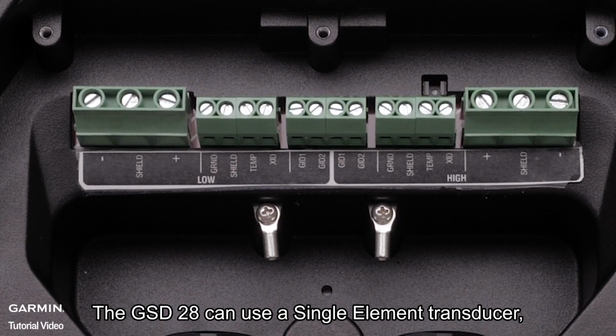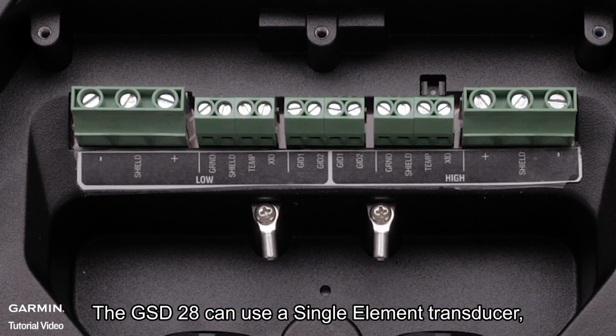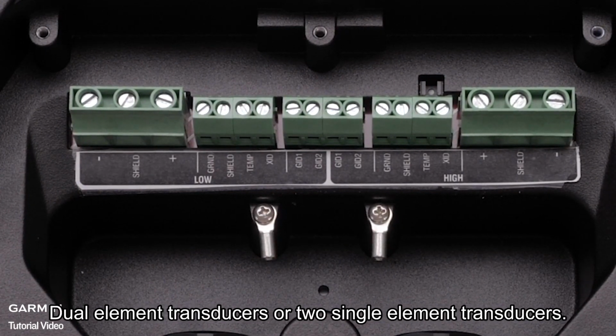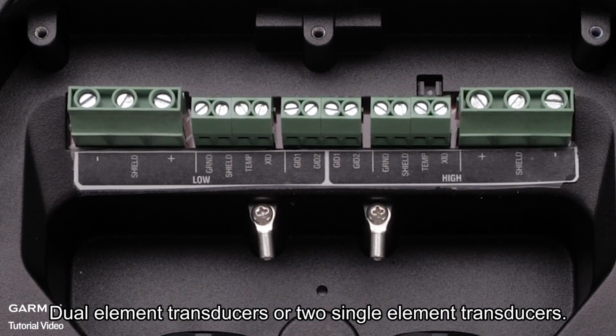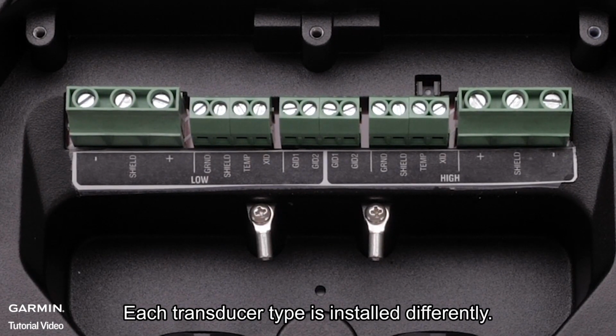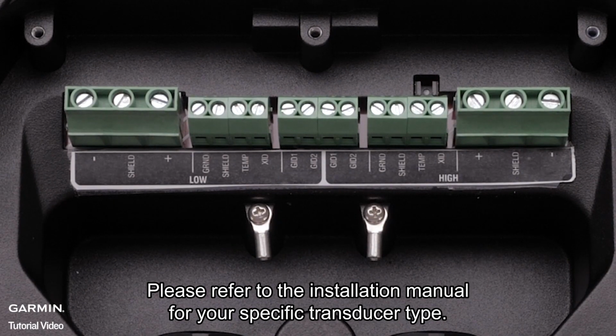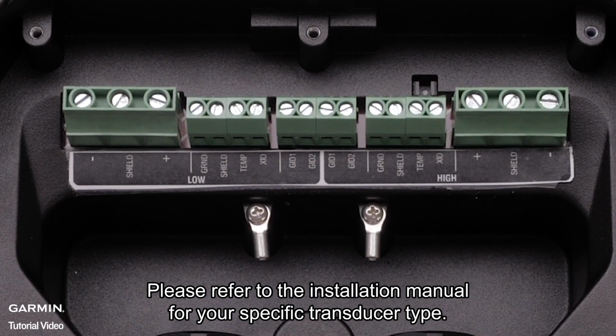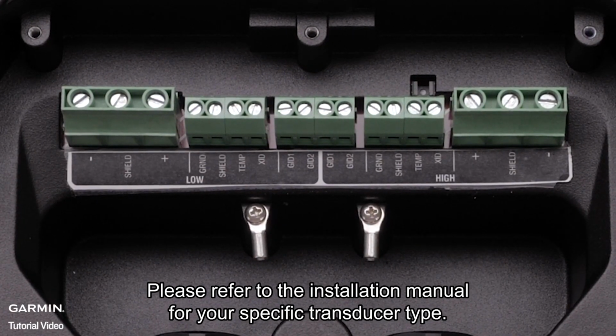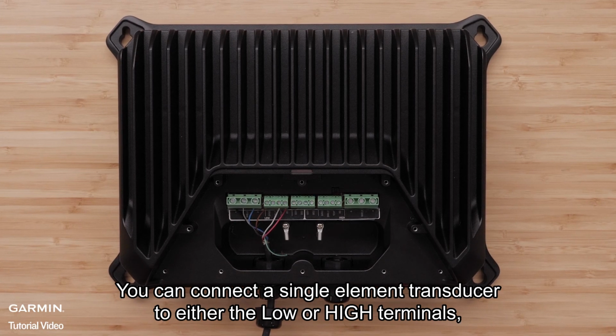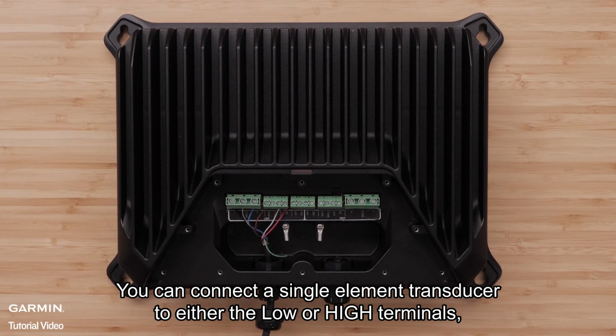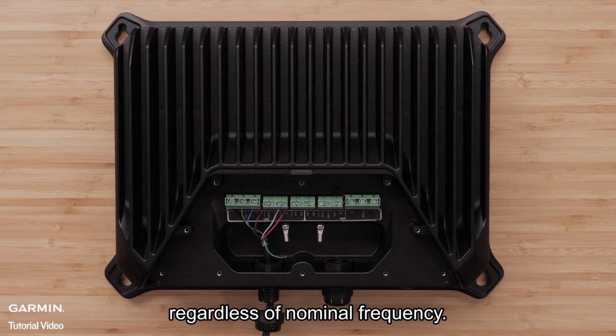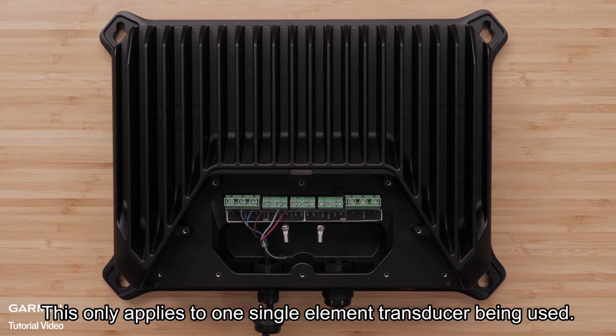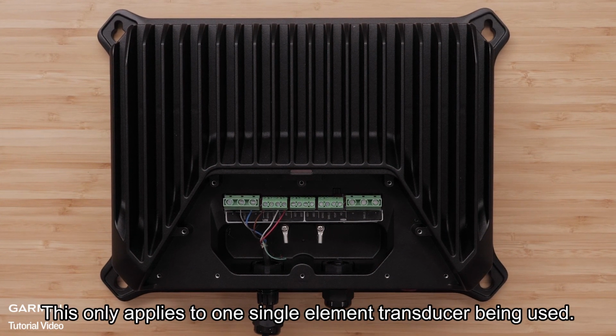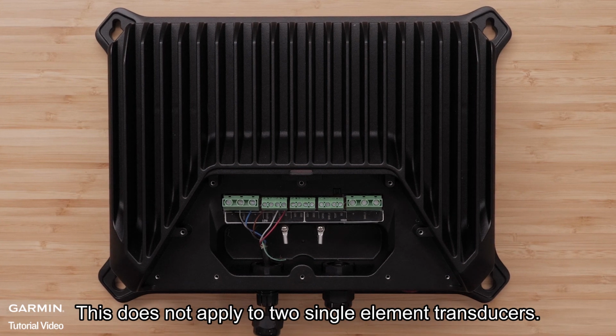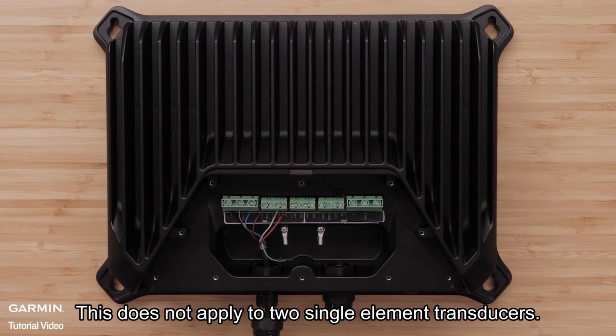The GSD 28 can use a single element transducer, dual element transducers, or 2 single element transducers. Each transducer type is installed differently. Please refer to the installation manual for your specific transducer type. You can connect a single element transducer to either the low or high terminals, regardless of nominal frequency. This only applies to one single element transducer being used. This does not apply to 2 single element transducers.